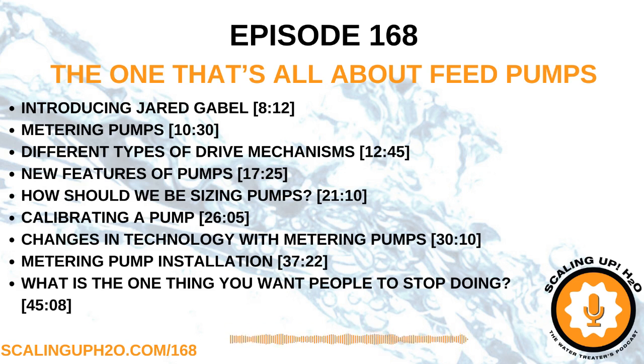So always be mindful of your suction piping, especially. Maybe you have to add a dampener on the suction side and also on the discharge side, because we want to make sure there's a scenario where, if you don't have enough back pressure on the discharge side of the pump, you can start siphoning and just dumping chemical when it's completely off. So the pumps, they don't have a stop inside the heads that doesn't allow the chemistry to push through it. So it always wants to go in one direction.